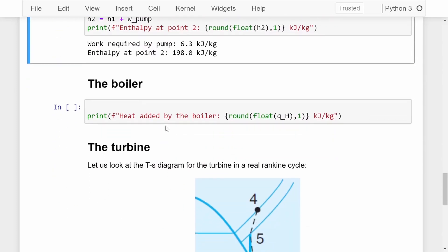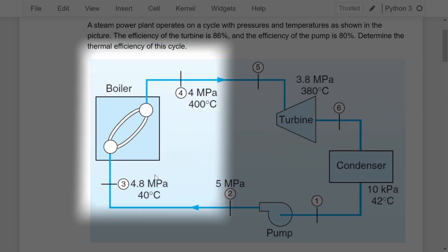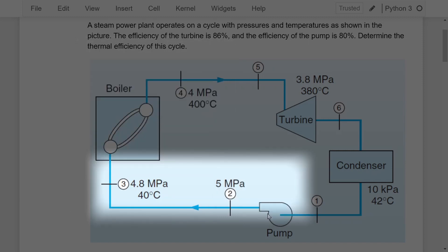Looking at the schematic for the boiler, we have values at points 3 and 4 with both pressures and temperatures given. There is a pressure drop between the outlet of the pump and the inlet of the boiler, from 5 MPa to 4.8 MPa. This is due to pressure losses, very common in a real Rankine cycle because the pipes transporting the water have friction and bends, causing a reduction in pressure. So the pressure at the outlet of the pump is not the same as at the inlet of the boiler.